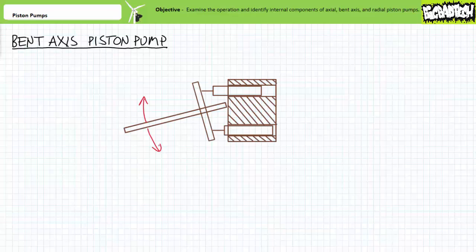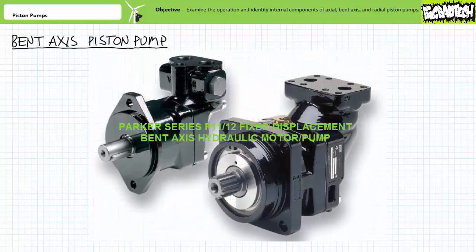If the drive shaft's angle to the piston block could be varied, this would be a variable displacement bent axis piston pump following the same principle: maximum angle, maximum flow; less angle, less flow; no angle, no flow. A bent axis piston pump is immediately recognizable as one having a noticeable bent axis, as one would expect.